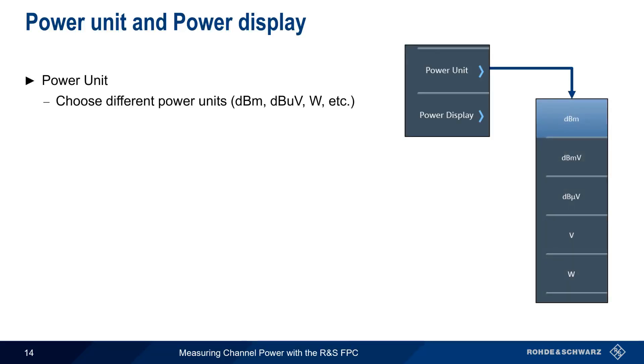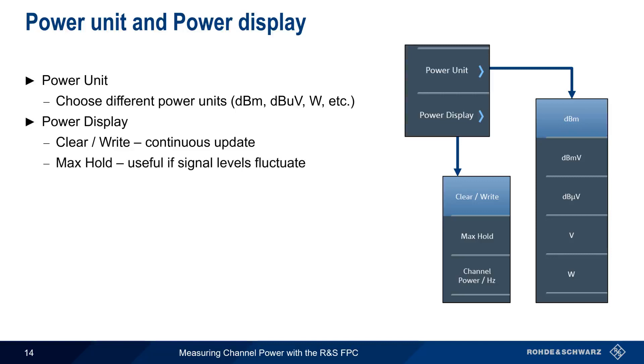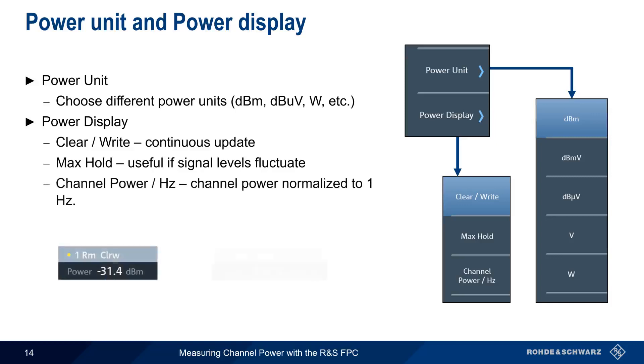Use Power Unit to choose the units of displayed power – dBm, dB microvolts, watts, etc. Power Display controls how the measurement results are presented. Clear Write is the default mode and updates the channel power measurement continuously. Max Hold shows only the maximum measured values, and this can be useful if the signal levels fluctuate. And Channel Power Per Hertz displays the channel power normalized to 1 Hz. For some applications, channel power is more commonly expressed in terms of power per hertz, instead of as total channel power.